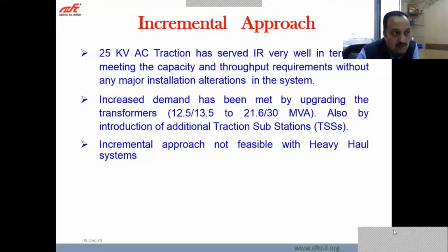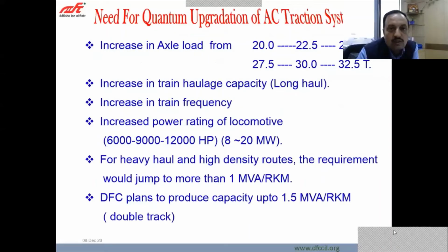But in case of freight traffic, what we envisage is that this incremental approach probably will not work out, and we have to execute a quantum upgradation of the AC traction system, because there is an increase in axle load. Earlier it was 20 ton, and we will be shifting to 25 ton immediately, and in future it will be upgraded up to 32.5 ton. So if we want an increase in axle load from 20 to 32.5 ton, there will be quantum upgradation of the complete system. We cannot go with the incremental change, that is, slightly changing the transformer or adding one or two switching posts. It will not work. For increasing the train haulage capacity, for running the long haul trains and for meeting the train frequency, we have to go for the quantum upgradation.